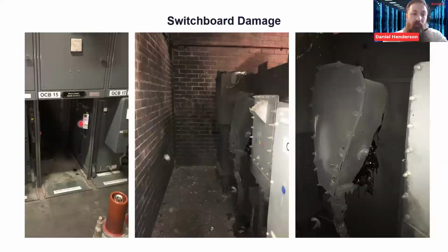So you've got carbon build up inside, mainly from the circuit shutter side of that. At the rear of the board, you've got quite a lot of contamination built up. So you can see the nice red bricks how it should be. This is all damage and debris from that expanding copper, that molten metal that's been thrown around in there. And this is the rear of the junction box. Again, compound filled. You wouldn't want to be in that location if it failed.